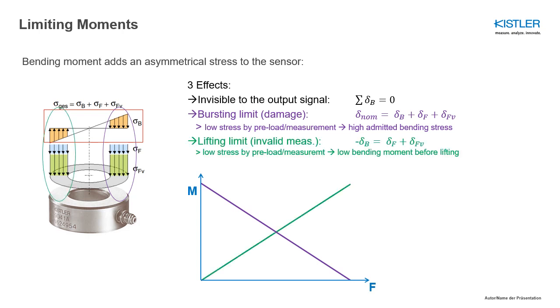On the other side of the sensor, you relieve the surface from stress. And the risk there is, as soon as the bending moment stress, or the stress relief, so to say, is higher than the sum of the preload force or stress and the process force, you risk to lift off the measurement structure from the surface, and your measurement is not valid anymore because the force that is applied to the sensor is not distributed evenly anymore. You can see it here on the graph as well. That means the higher your force is that you apply, the higher the bending moment, or the negative stress from the bending moment, is allowed to be applied as well.